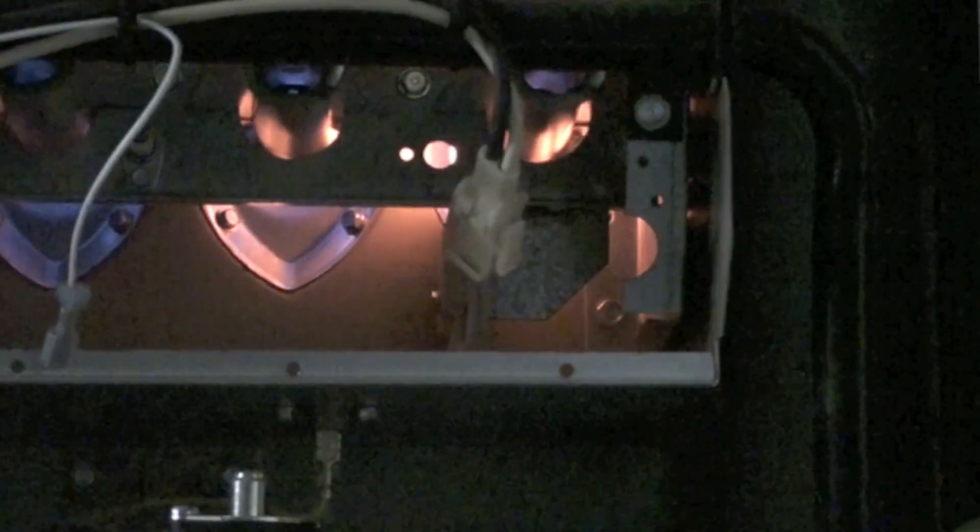The hot surface igniter's come back on. It will make another attempt to light. There it goes. It has not sensed flame so the gas valve is shut off and it'll try again.